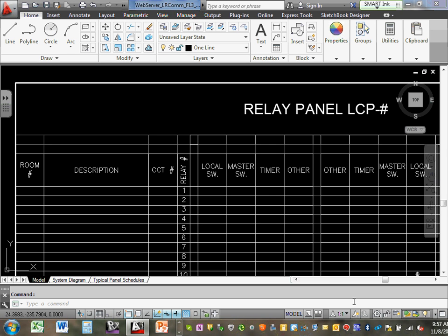So we know what the room was, we've given it a description, we talked about which circuit it is. Now LP1 could be LP1-1, 1-1, because what I'm doing is breaking down that single circuit into switch loads, right? And I'm doing it at the relay level, not at the classroom level. So now I've taken circuit 1 and I've broken it down into 5 or 6 or whatever number of switched legs that I want to have, because I'm going to do different things with it, right?